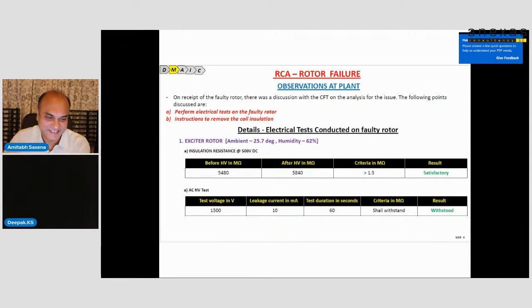Yes, we performed the electrical test on the faulty rotor. First was the exciter rotor, which is part of the faulty rotor. We checked the insulation resistance. Yes, it is okay, not an issue. It meets the criteria. And we also did the high voltage test on the exciter rotor. Yes, it withstood.